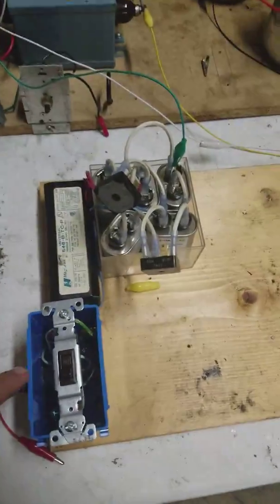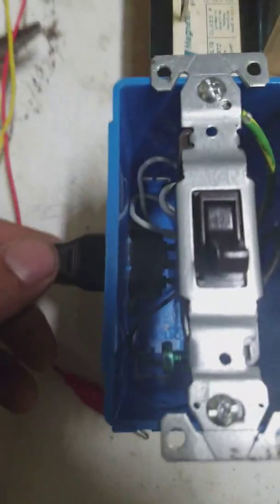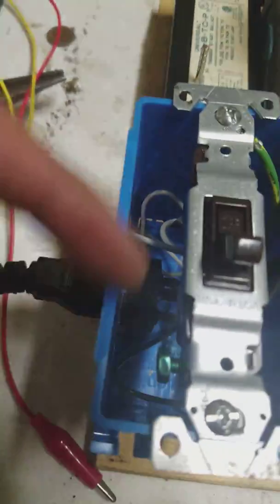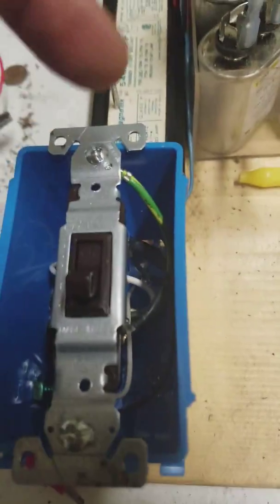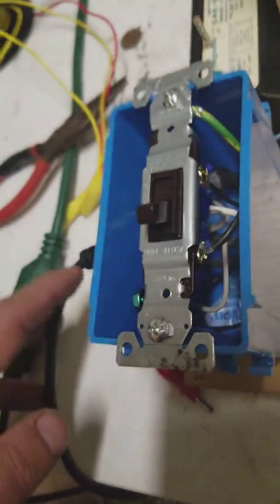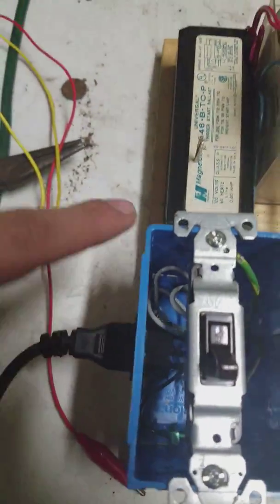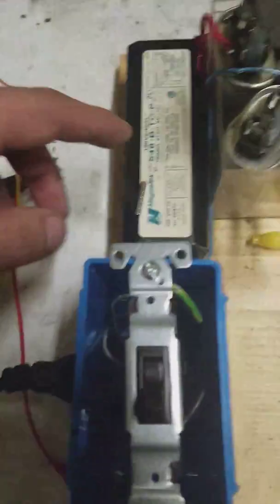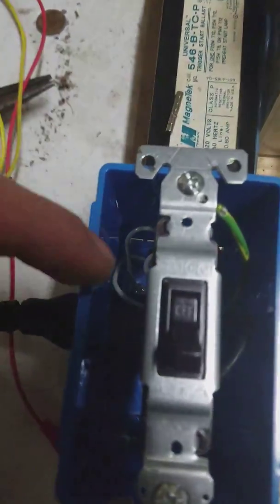This is plugged in straight to here, which is just using the white wire. This is all factory made connections, they were pre-soldered on there: black, white, and green. Black is going to the switch. Switch is open. White is passed straight through with a wire nut to the ballast, to the white wire on the ballast. The black wire on the ballast goes to the switch also.